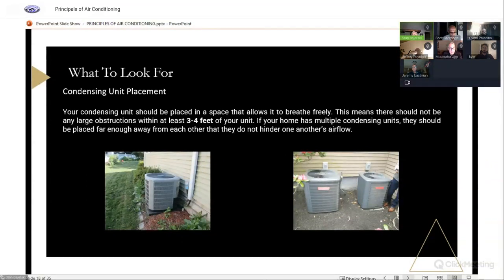Same thing with dryer venting. That's got to be away from the unit too, because lint can get into the units. Correct. It's funny, just about a month ago, somebody put this big net over the condensing unit because of the dryer vent. See where this disconnect is? Let's say that was a dryer vent. It was blowing the lint on this unit. So you plug up the net instead of the coil. Maybe it's easier to clean, but you're still restricting the airflow there. That dryer vent should be moved.